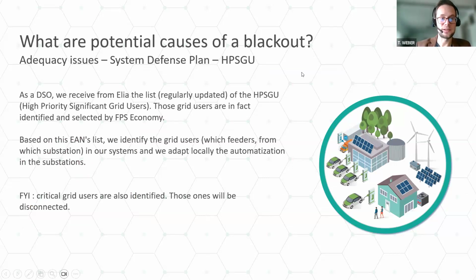So as I've explained, we receive from ELIA, but in the end it's from the FPS Economy, regularly, typically once a year, an update of the high priority significant grid users. And we need to identify these customers. Typically, it's the EAN of the customer we receive, and we have to check this EAN. How is it fed on our network? Is it connected to this or this substation? Because it's important for us to update the local automation in the substation. As I've said, some feeders are not tripped in the selective load shedding, but it's important to keep it up to date. So that's how it works. Every year we have an update and we make it.